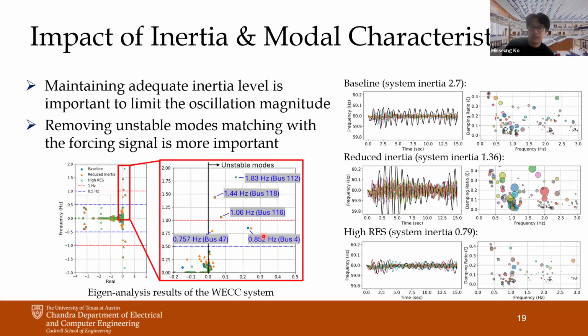But when we replace the synchronous generators with renewable energy sources, you can see that these unstable modes are removed, and they change into higher frequency unstable modes and lower frequency unstable modes. So even though the system has a lower inertia level, there is no amplification by the systemic modal characteristics at this 1 Hertz frequency. This would be the reason why the high renewable energy source cases have a lower magnitude of oscillation.